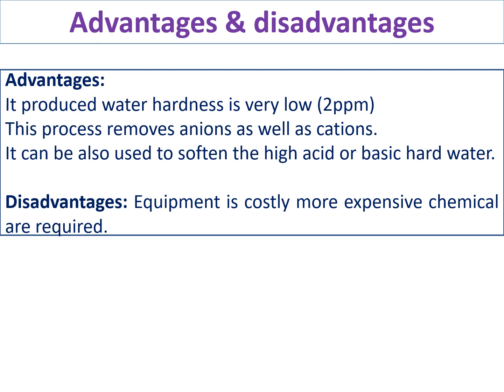Advantages of this process: it produces water with hardness below 2 ppm, making it ideal for industrial applications. It removes both anions and cations, producing deionized water, and is applicable to highly acidic or highly basic water as well. The only disadvantage is equipment cost and the use of many chemicals. However, industries can afford this because they need pure soft water — passing soft water into boilers avoids problems like corrosion, scale, sludge formation, and foaming.